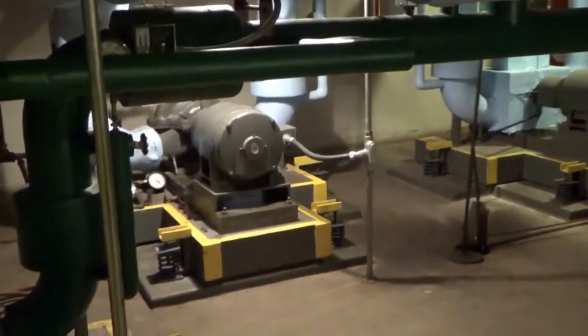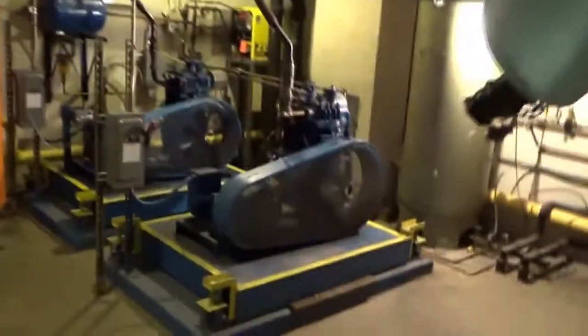Again, this is MP1. If the pump goes down, we can turn that back pump on, the secondary pump, by just closing and opening a couple valves on the system and diverting that water over. Once the valves are operated and in the correct position, inside this cabinet is a switch, and all the person needs to do is toggle that switch to the other pump, and the pump MP1 will shut off and the auxiliary will turn on.